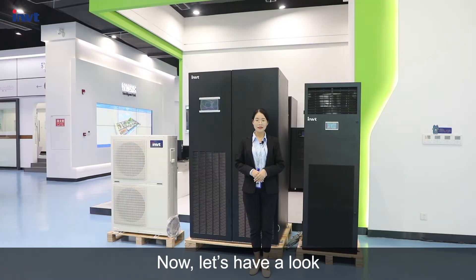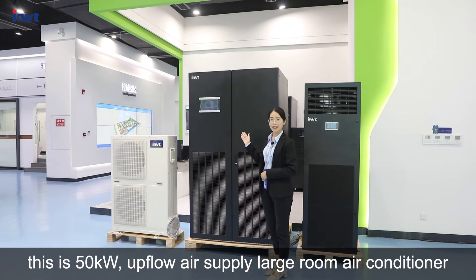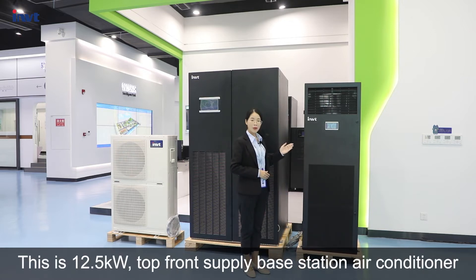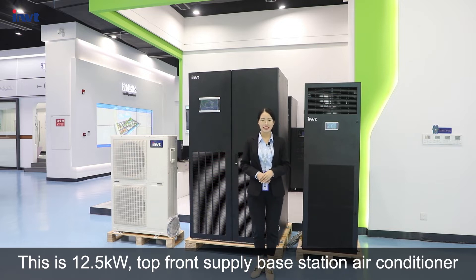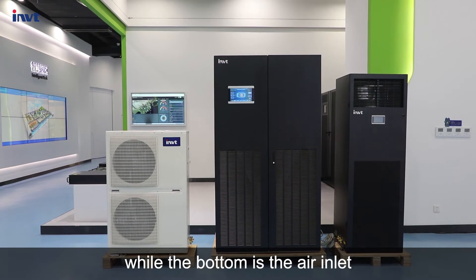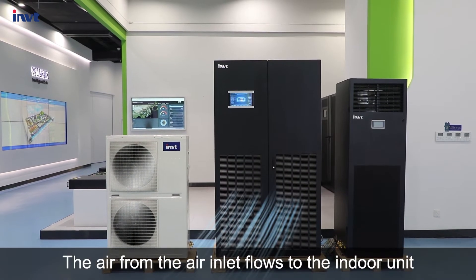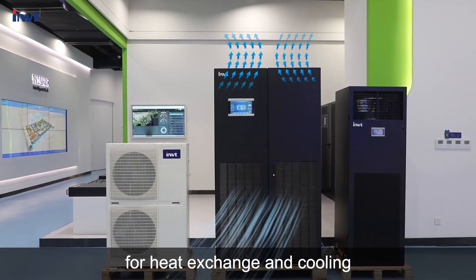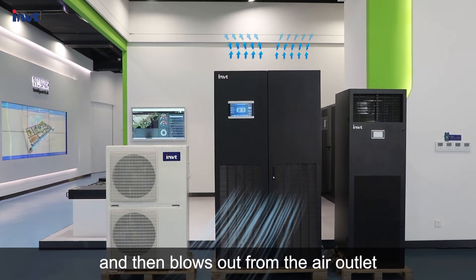Now let's have a look. This is a 50 kilowatt upflow air supply large-room air conditioner. It is a single system. This is a 12.5 kilowatt top-front air supply base station air conditioner. At the top of the air conditioner is the air outlet, while the bottom is the air inlet. The air from the air inlet flows to the indoor unit for heat exchange and cooling, and then blows out from the air outlet.